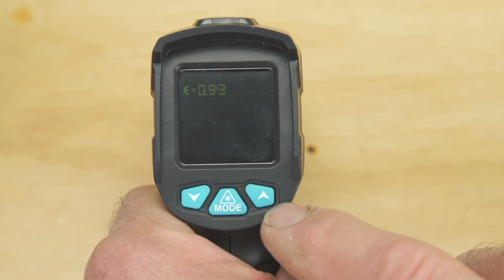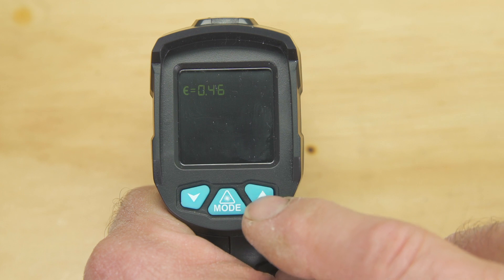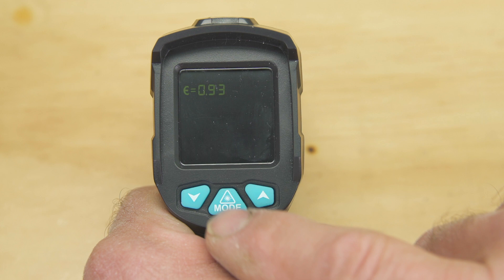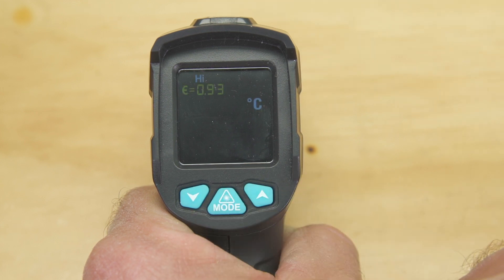Another press of the mode button and we can set the emissivity figure. Here we're stopping at 0.93, which is the emissivity setting for water. A further press of the button and we can choose either centigrade or Fahrenheit as our scale. And a final press of the button gets us back to the beginning.